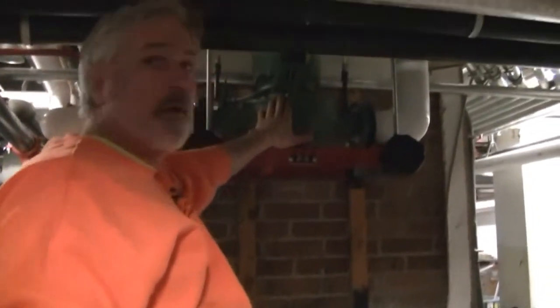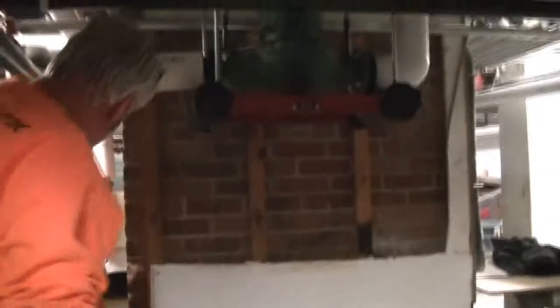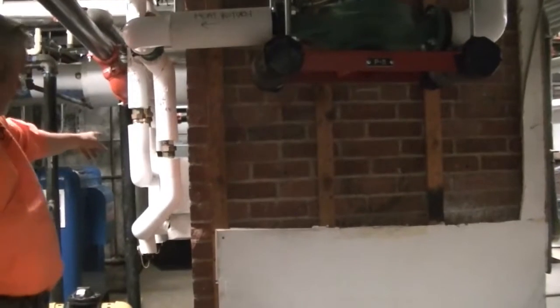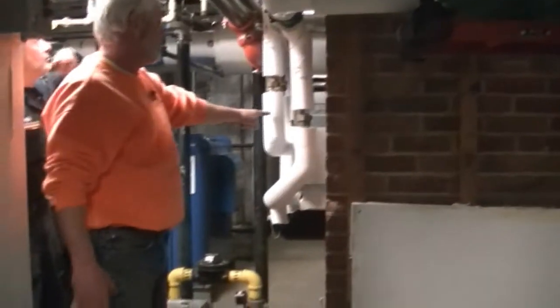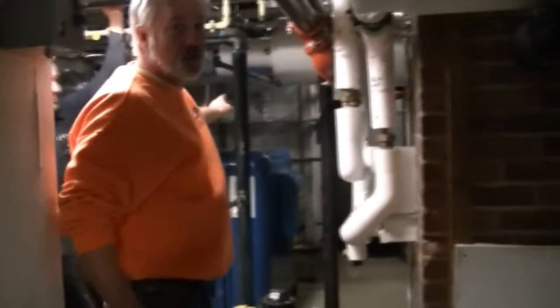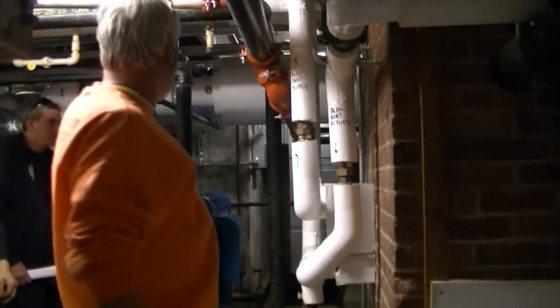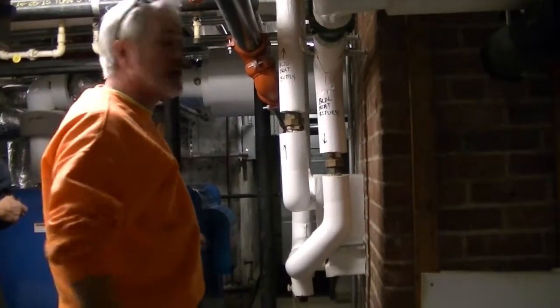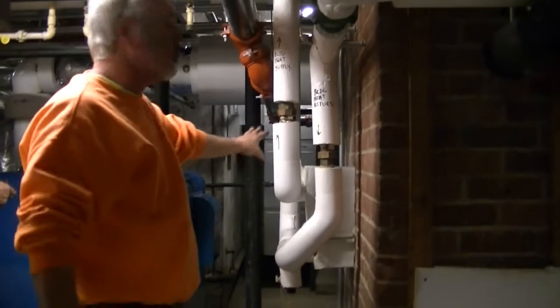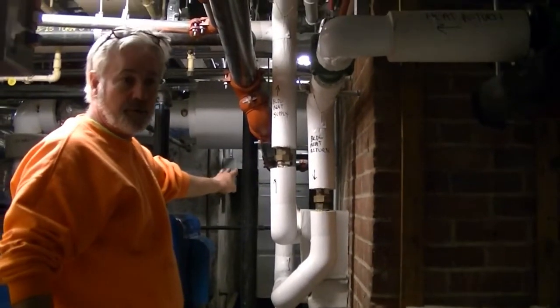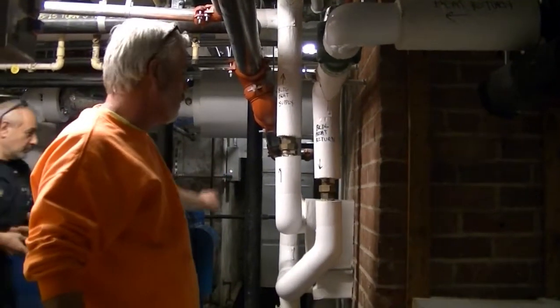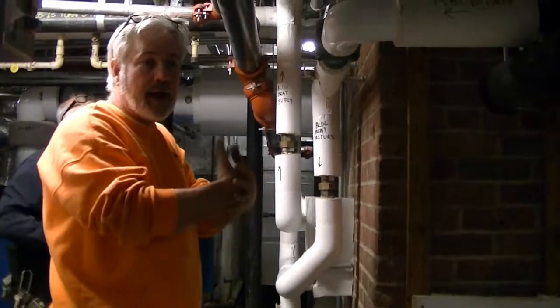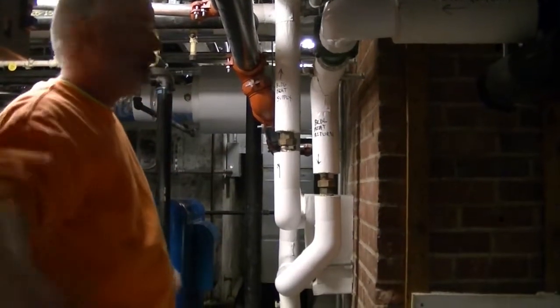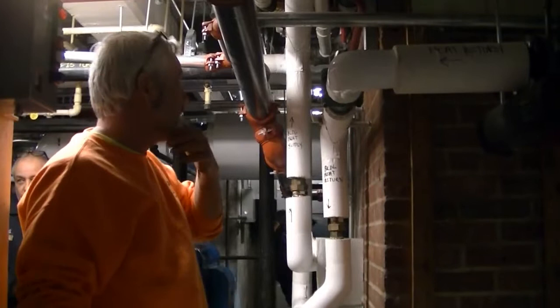This pumps water out of the boiler system through a plate heat exchanger that picks up the heat off the cogen. This is how you get that primary heat off of that cogen. The cogen has its own closed loop fluid system and a cooling system in it. All we do is transfer that heat over to the heating system, and that's where you get that heat.